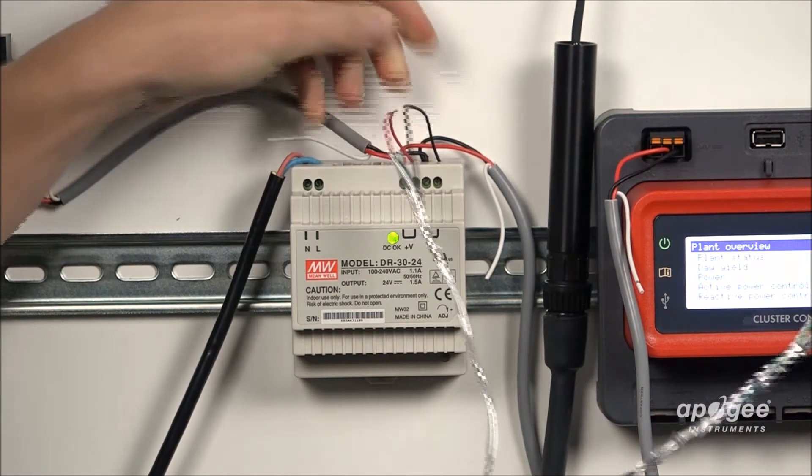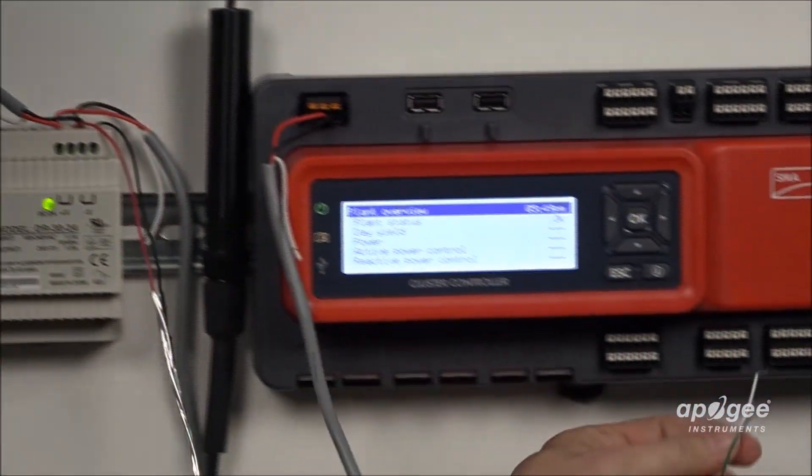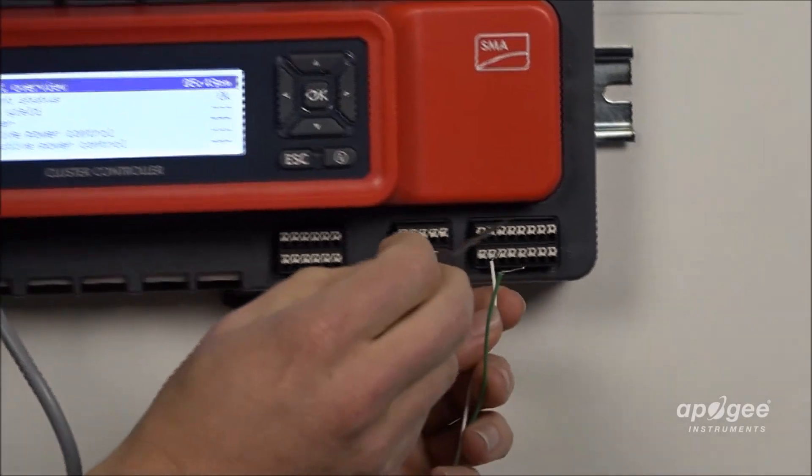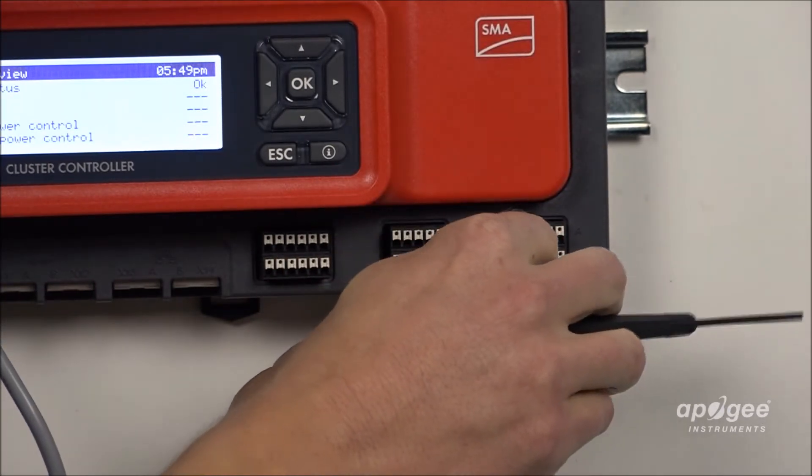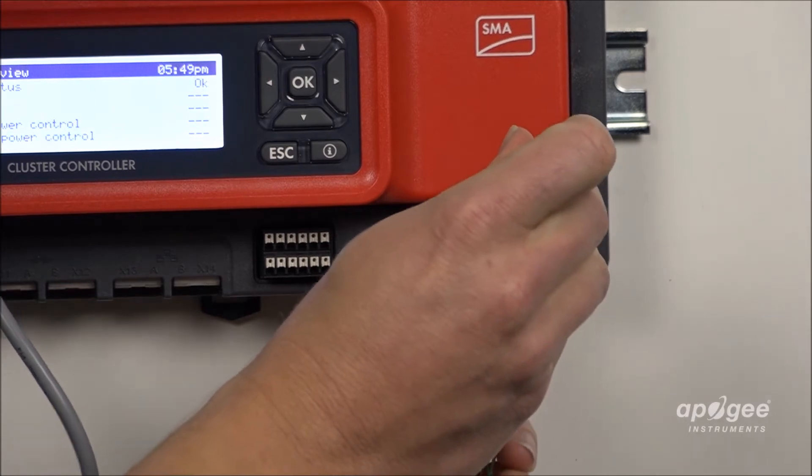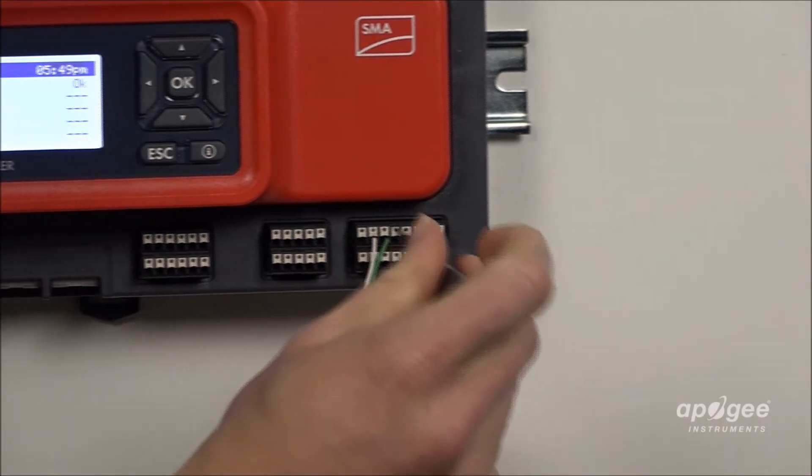Over here on the controller itself we are on X8 and the top row is A2 so we're going to go in A2 for the white conductor, A3 for the green conductor and these are just push in terminals so they just push in and then our shield we will go into A4.